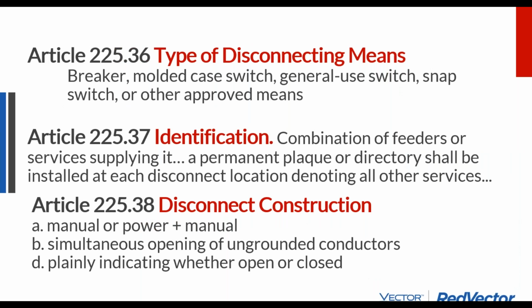The type of disconnect switch can be all over the place. You don't always need a knife switch. A knife switch disconnect and a breaker are both disconnect switches. We have a call out for identifying whatever feeders are supplying a panel. And so it's not solar discrimination to say you have a solar array, you need a one-line diagram that shows how the power enters the building. When you have a combination of feeders, a directory explaining where they're going is required. Disconnect switches need to be manual. If they're powered, there needs to be also a manual option.